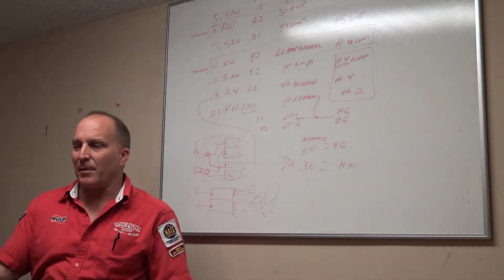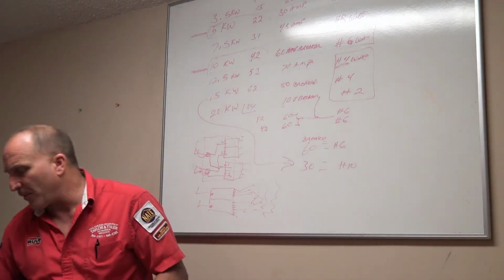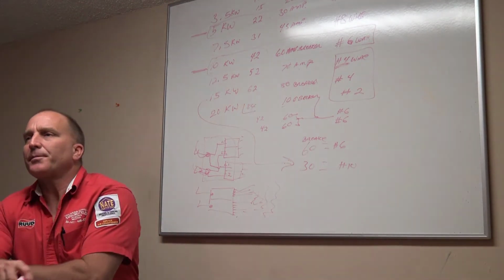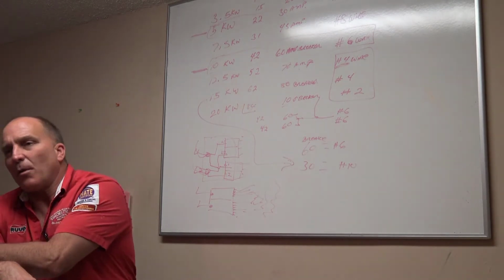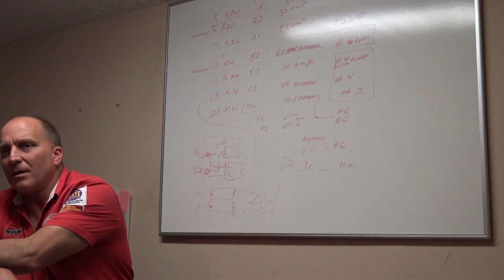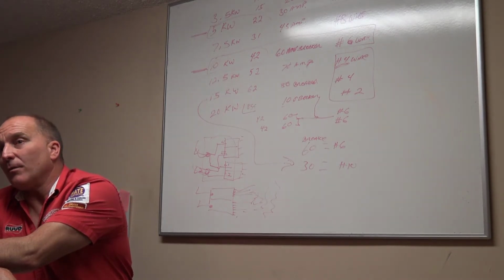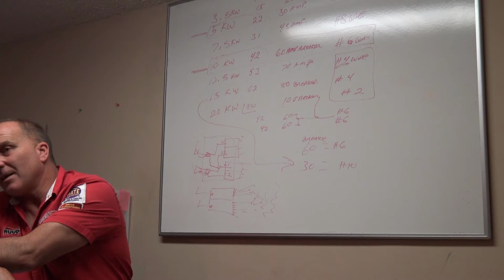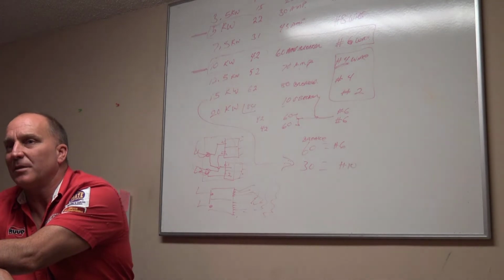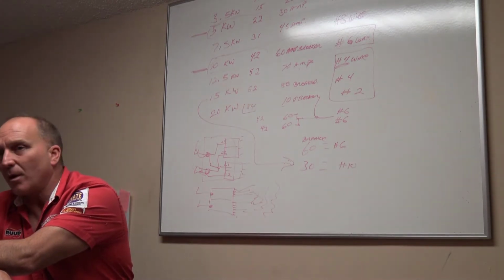Okay? As soon as you turn it on, somebody put a 15 kW heat system in and they forgot to disconnect 5 kW of the heat. So I'm going to say we sold a 15 kW heat strip on this particular air handler, whatever it is, and when we got there, we went, oh no, it's only got a number 6 wire to it. So I'm going to disconnect 5 kW of the heat. And if I disconnect 5 kW of the heat, that means I'm literally going to pull a wire off of the actual heating elements themselves, and you can't actually make this run again unless you literally go take the wire and put it back on.